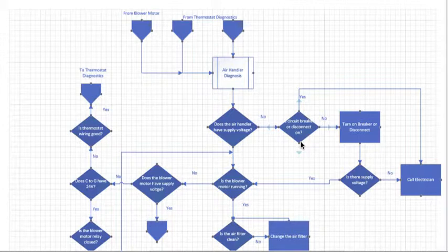If the breaker is already on and you don't have supply voltage, in most states you're not allowed to trace it any further in terms of what's wrong. You've got to call an electrician, because at this point there is a wiring problem or a problem inside the breaker panel or with the disconnect directly. Most states and jurisdictions allow the HVAC tech to work from the disconnect or breaker to the unit. Anything that is not a direct connection is an electrician's responsibility, especially if there's wiring in the wall or along the attic ceilings.